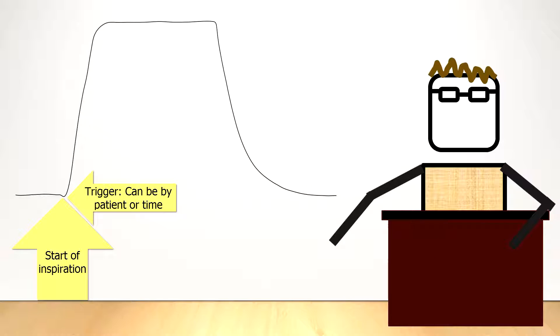So, for example, if the frequency set on the ventilator is 15 breaths per minute, then the ventilator will be automatically triggered to deliver a breath if 4 seconds goes by.